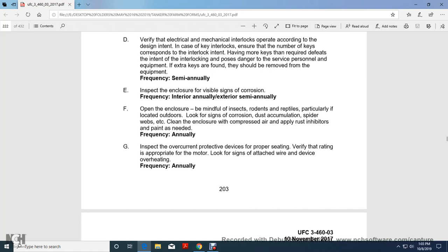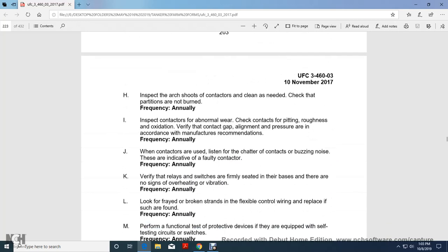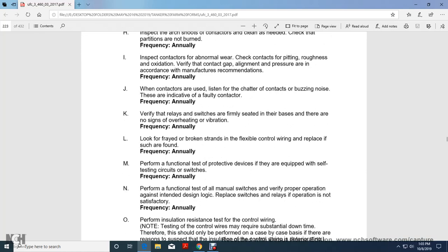Look for signs of the wire or device operating overheated. Inspect the arc chute within the contactor and clean as needed, checking whether the partitions are not burned, annually. Inspect the contactor for abnormal wear, checking for contact pitting, roughness, and oxidization. Verify that the contact gap, alignment, and pressure are in accordance with the manufacturer recommendations, annually.